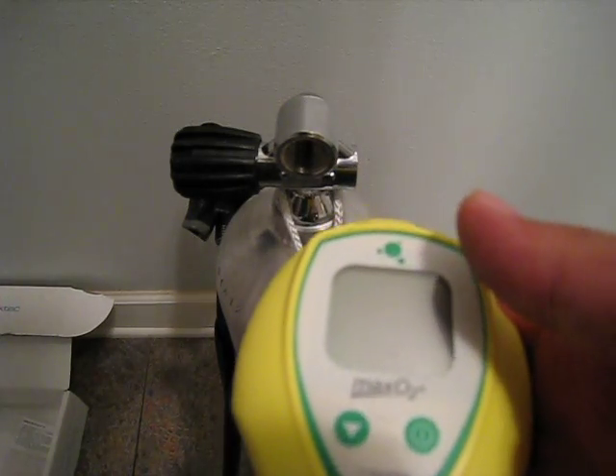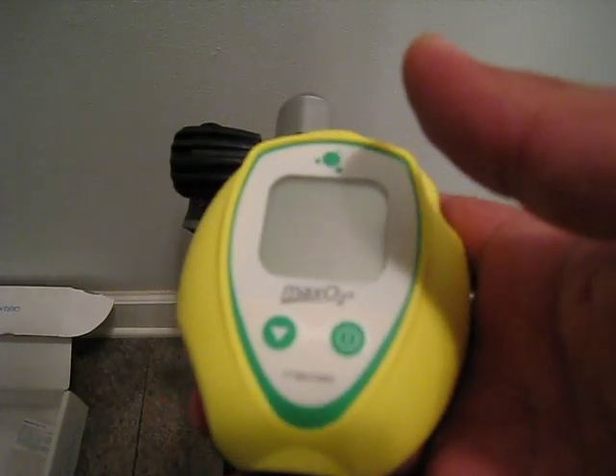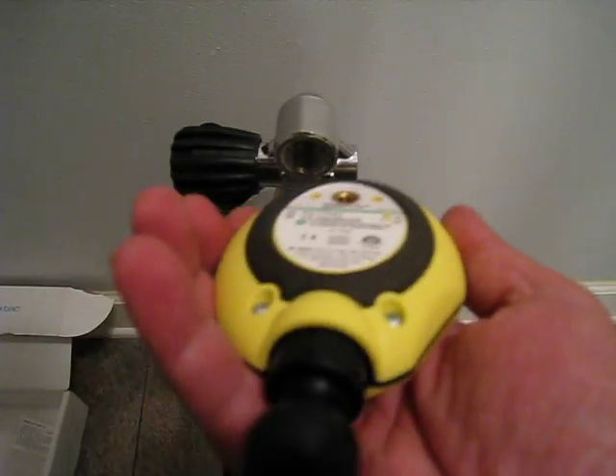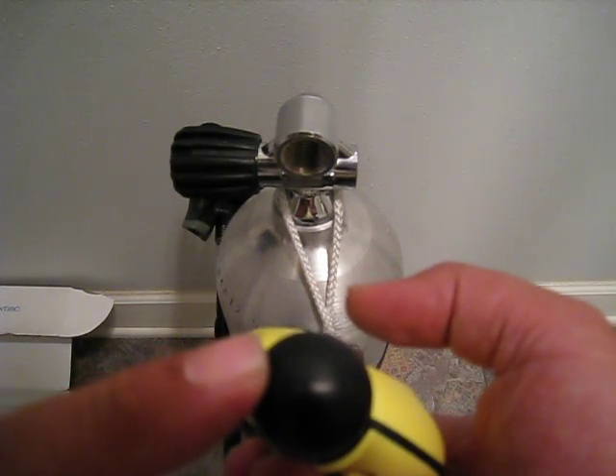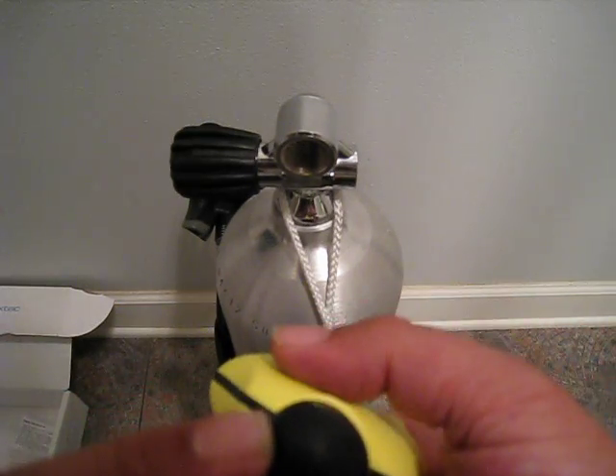Today I'm reviewing the Maxtec Max O2 Analyzer. As you can see, it comes in an ABS plastic housing that's really rugged. You can also attach a cord here if you want. It has a little nipple to reduce the flow of air into the unit so your sensor doesn't burn out as fast.